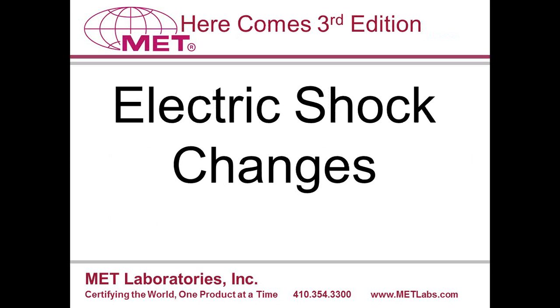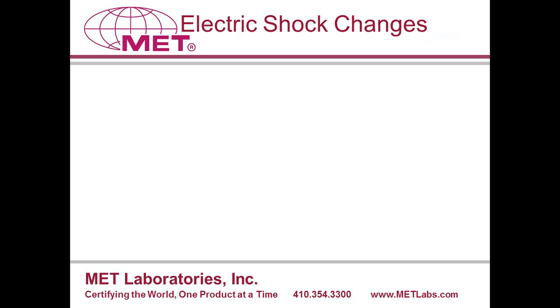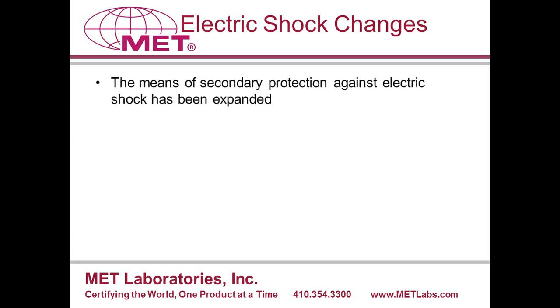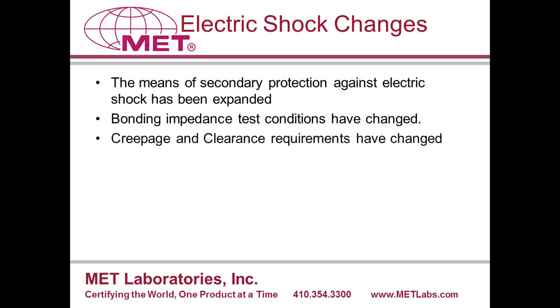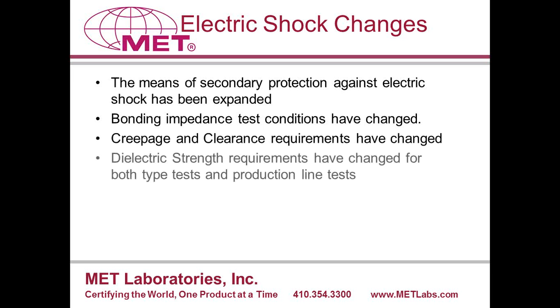Now let's talk about changes to the standard in electric shock design and testing. There are 4 major changes to how the 3rd edition addresses electric shock. First, the way that you can protect an accessible part from electric shock has been expanded. Next, the bonding impedance test has changed drastically for North American products. The creepage and clearance requirements have been greatly expanded, and the dielectric strength test requirements have become more severe.